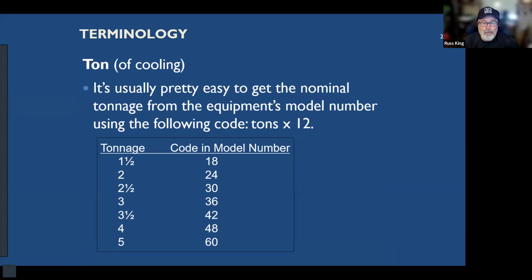So how do you look at a model number and determine the tonnage? Well, if you take that 12,000 and just think of the 12, look at the number 12. And if you take 1.5 and you multiply that times 12, you get an 18. In other words, 18,000. All right. You take the 2 times 12, you get 24. The 2.5 times 12, you get 30, and so on. So you get these numbers right here. So usually what the manufacturer does is they take this number and they will insert it into the model number of the air conditioner itself. Okay. So let's look at some examples.